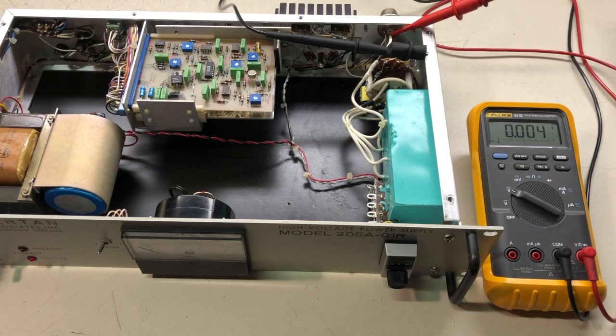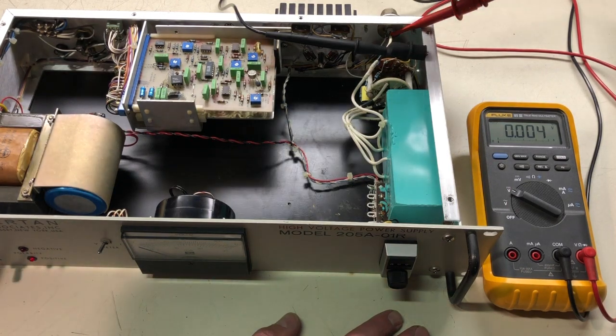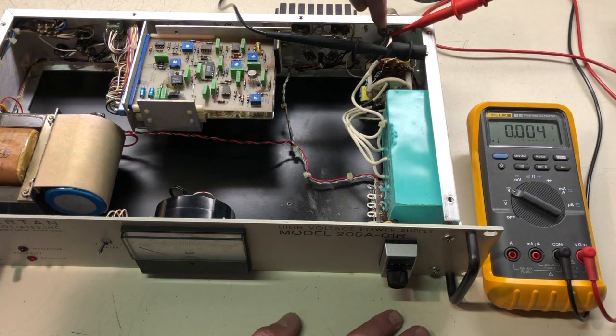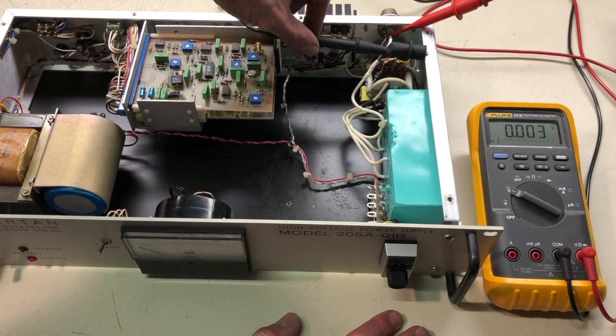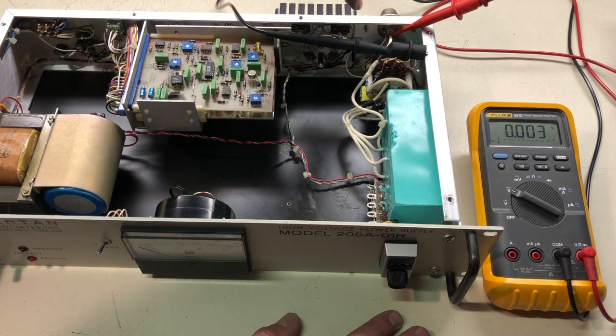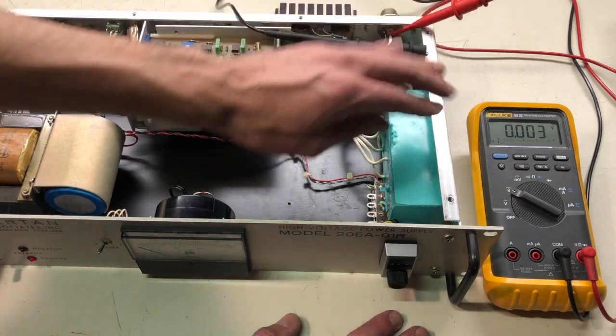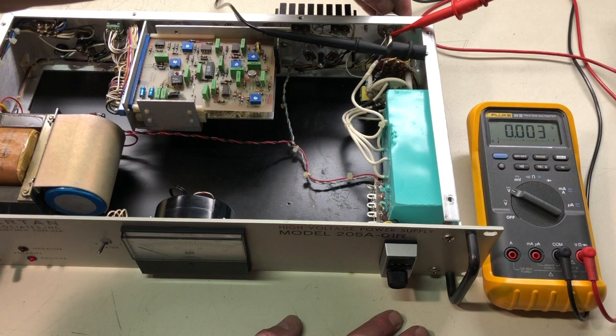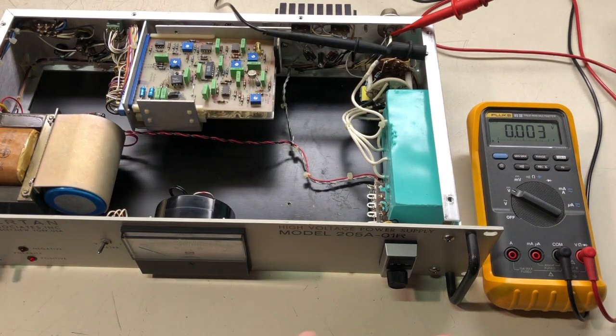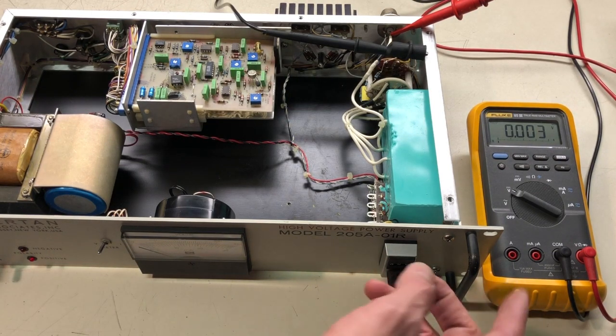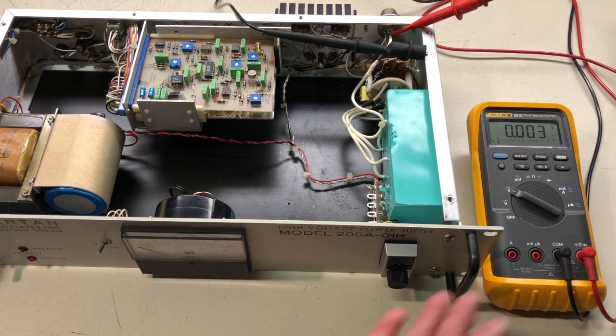Okay, I have the power supply turned on and the voltmeter is connected to the output connector. This lead is clipped to the output high voltage lead, and this is on the ground connection. This wire that's the ground on the output does tie to the chassis ground, so I've just clipped it to the chassis right here rather than trying to get into the connector. And the voltmeter is auto ranging, so it says 3 millivolts right now, but it will change the scale as we increase the voltage.